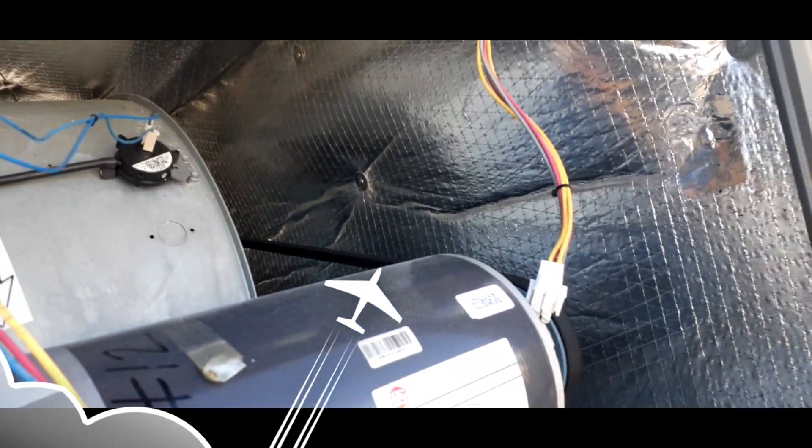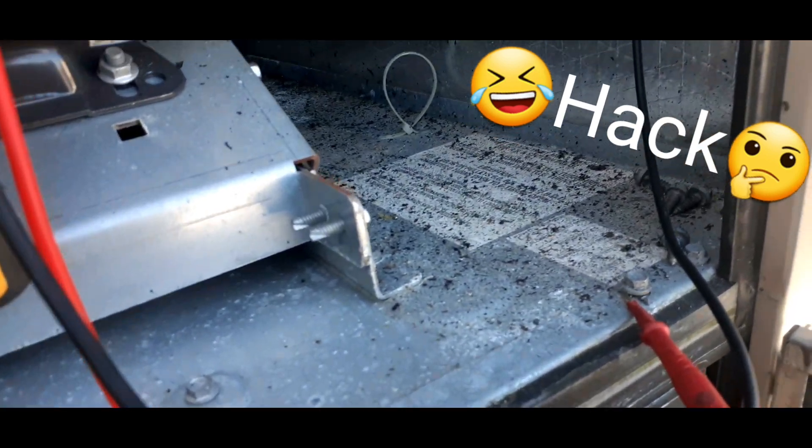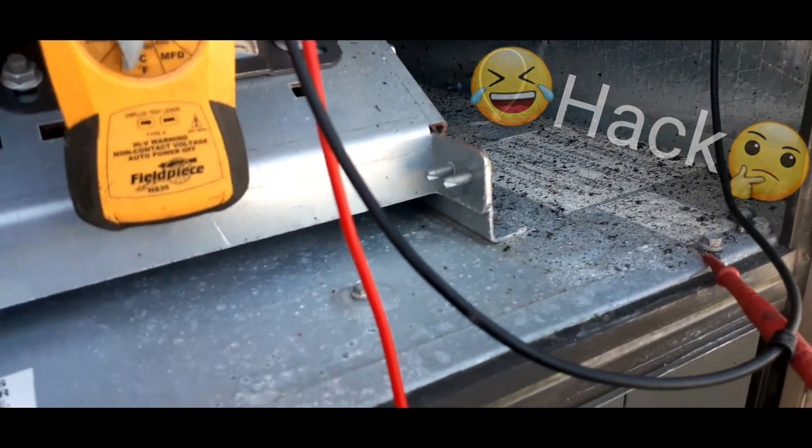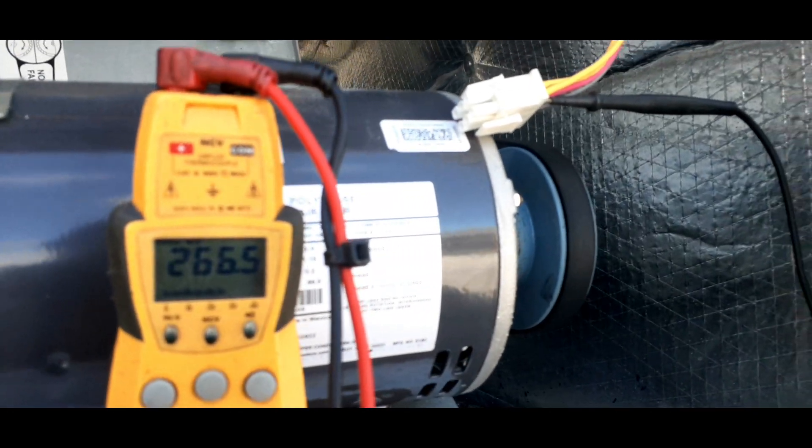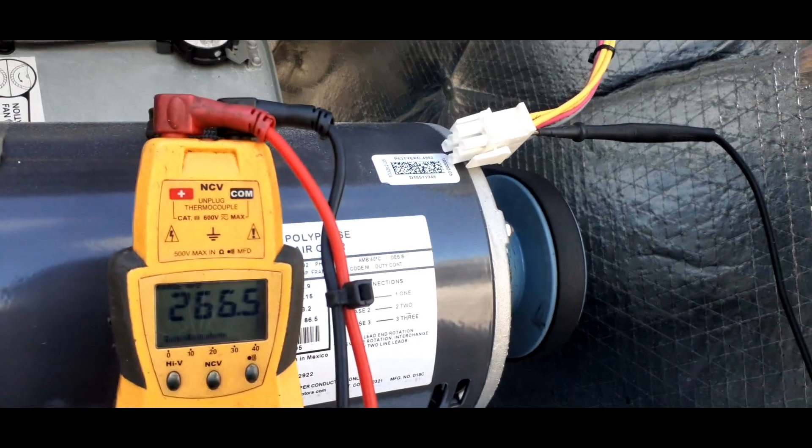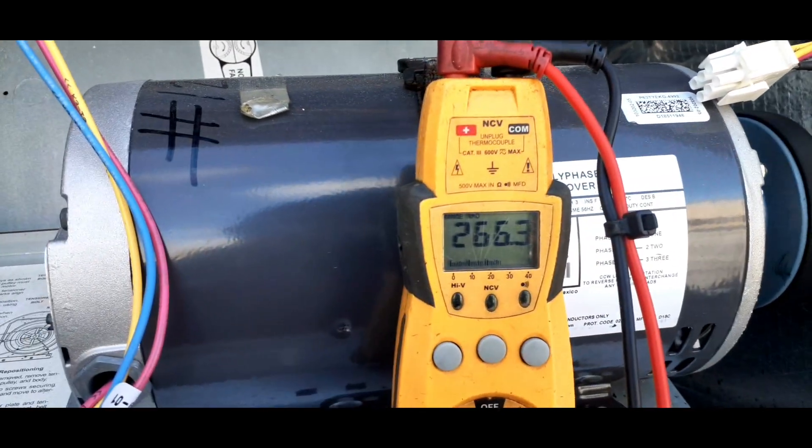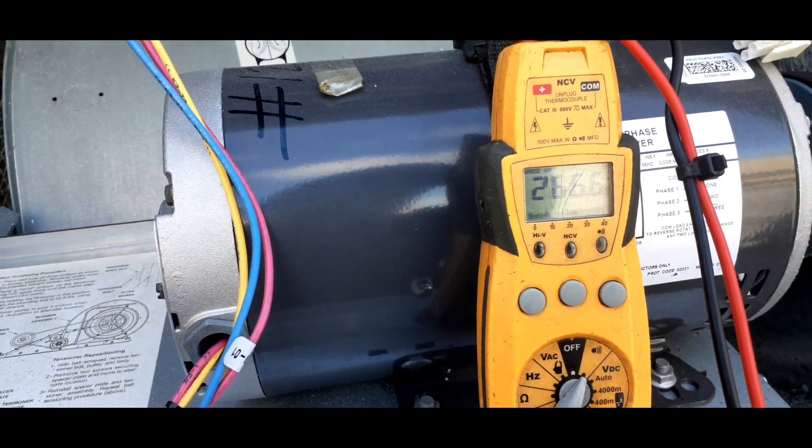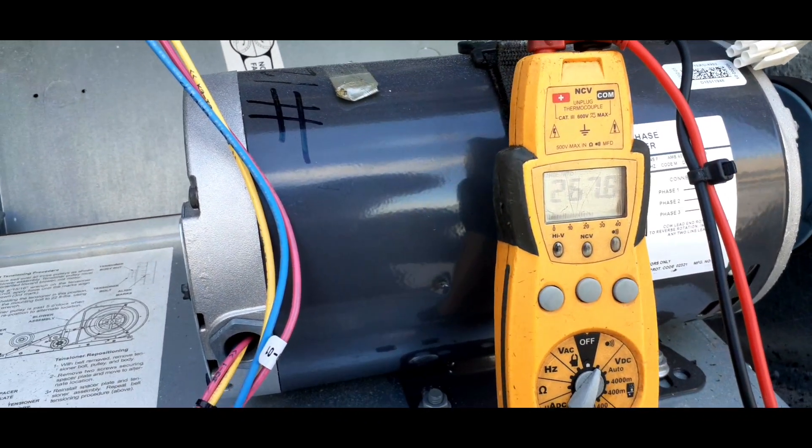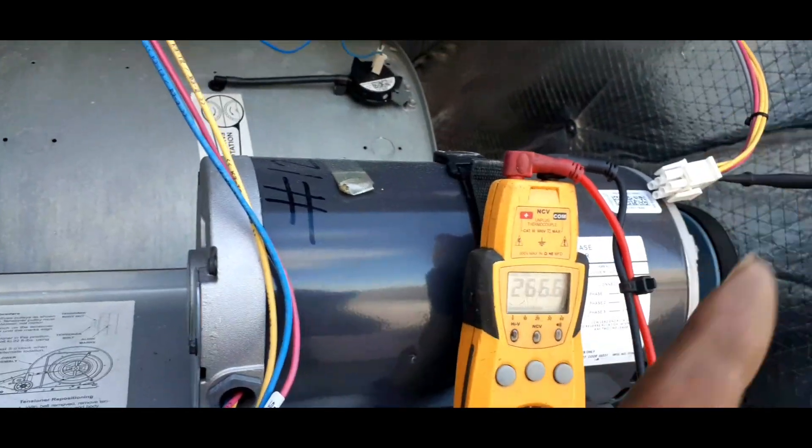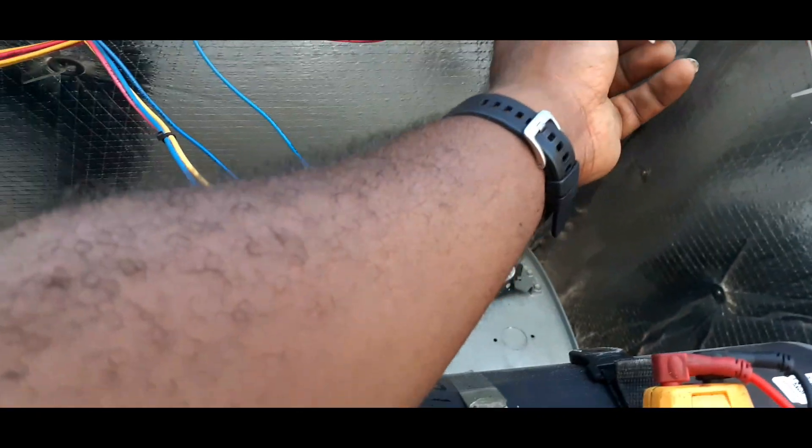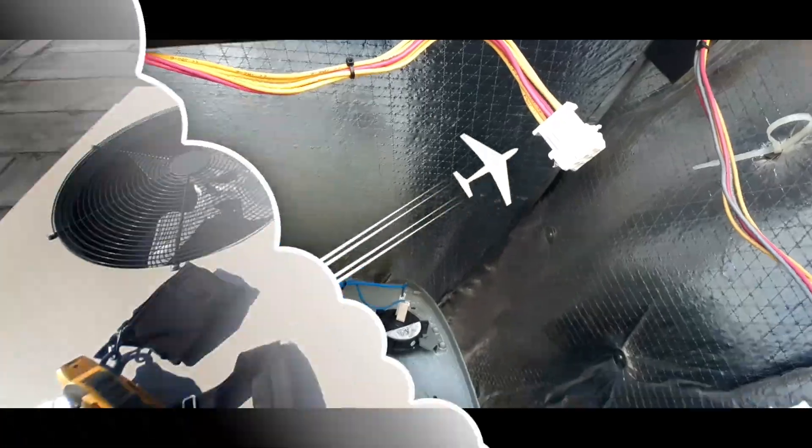All right, so what I did was, since I'm holding the phone, I put my other lead right here underneath that screw and I'm using the other lead right here to check for continuity. And as you can see, we're picking up some resistance to ground, 267, so our issue is going that way. I did check these wires going back the other way, there's no issue.